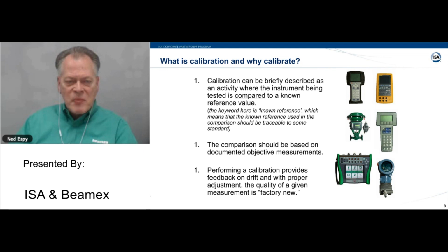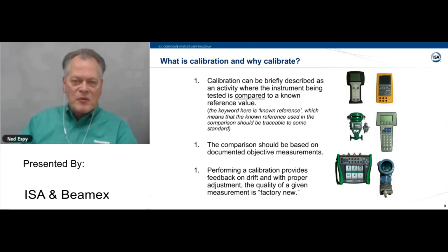Also, when you make this comparison, the calibration typically involves documentation. People either write the numbers down or record the data some way. And the bottom line is, after you perform a calibration, if there has been drift and you've made proper adjustments, you're essentially making the instrument factory new, as when it was first shipped to you.